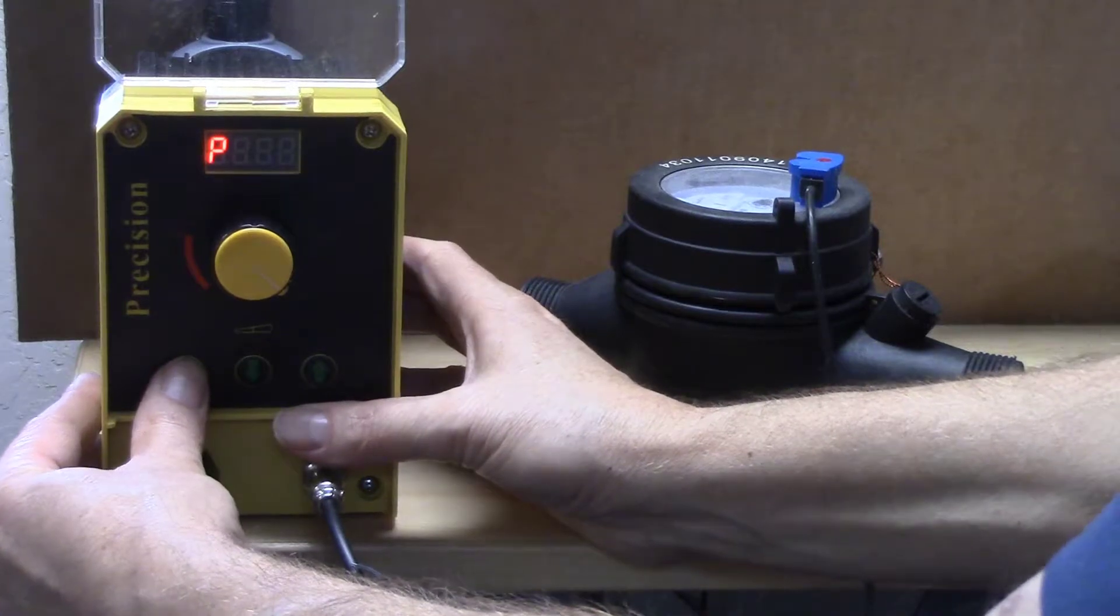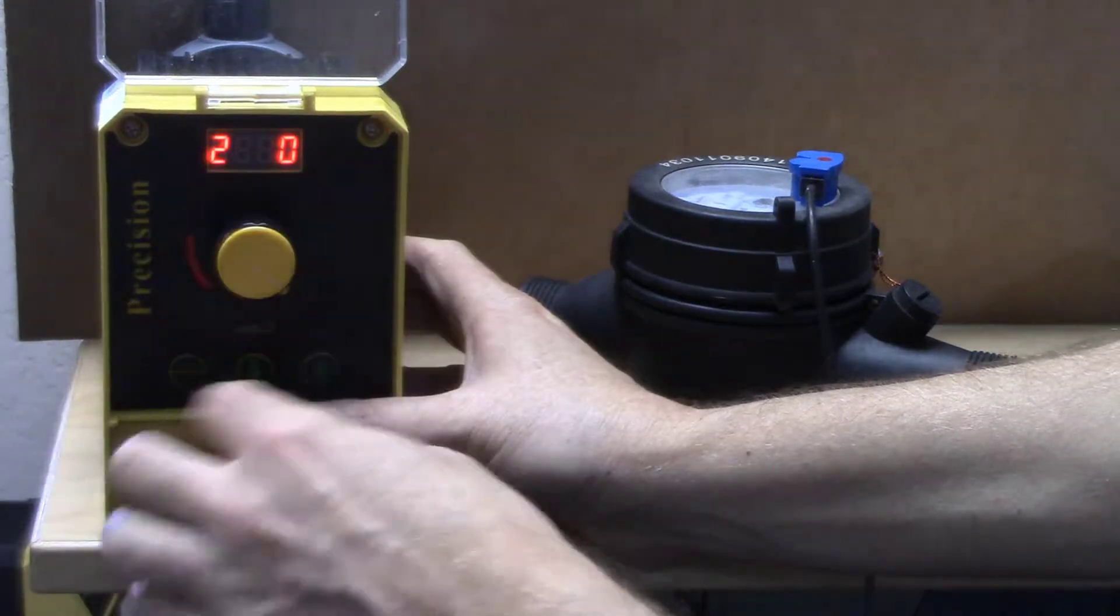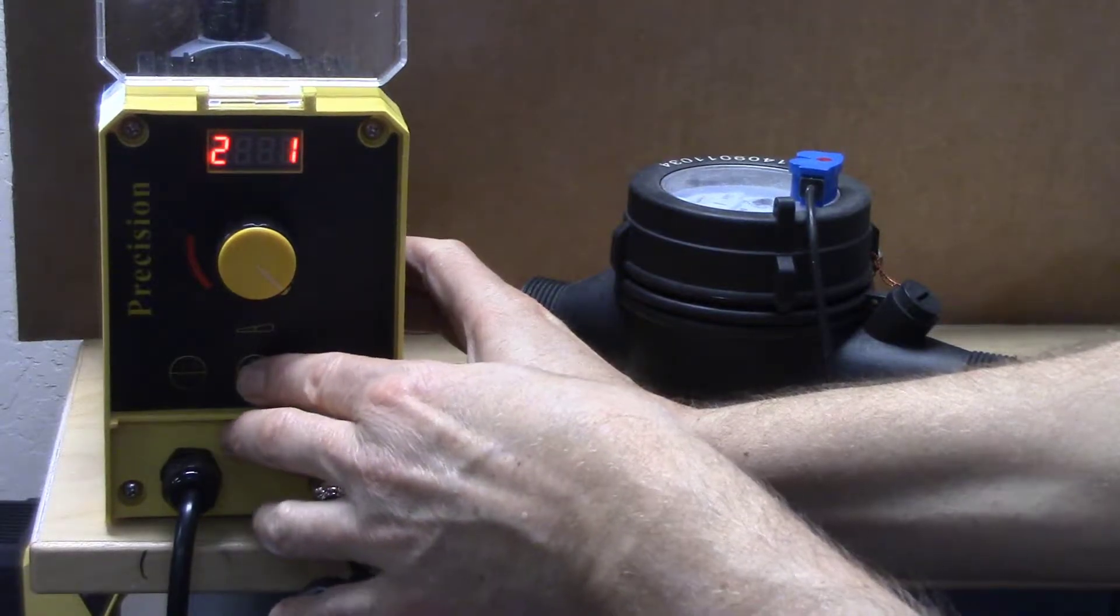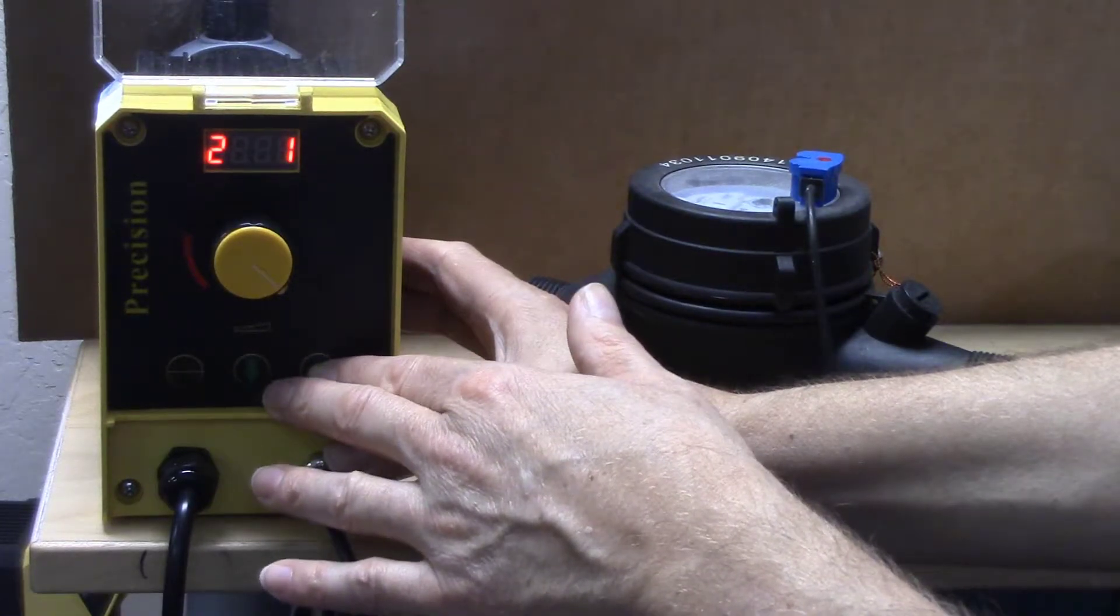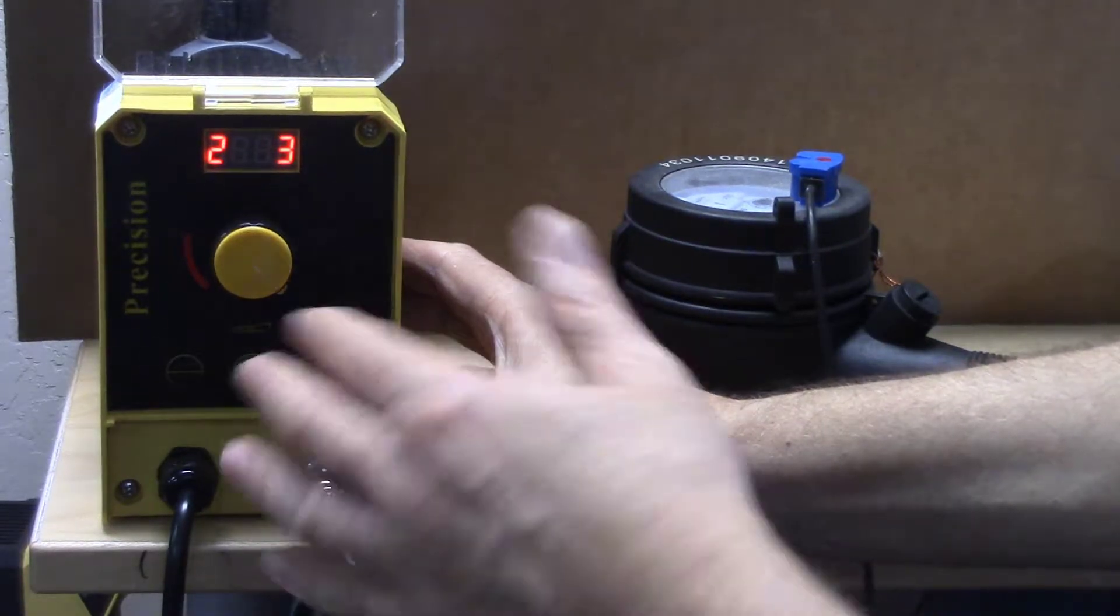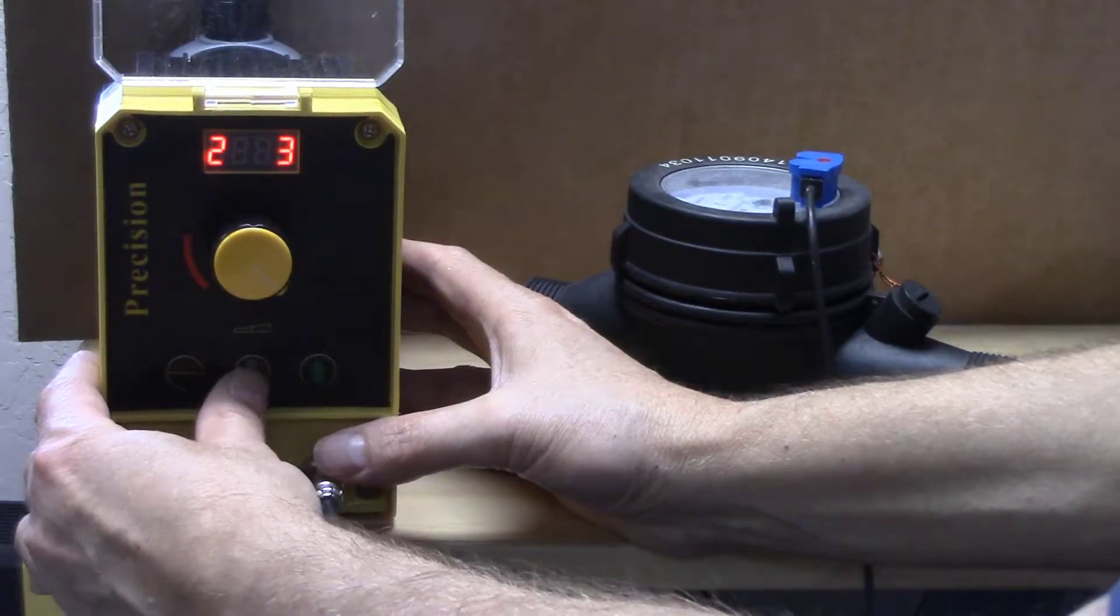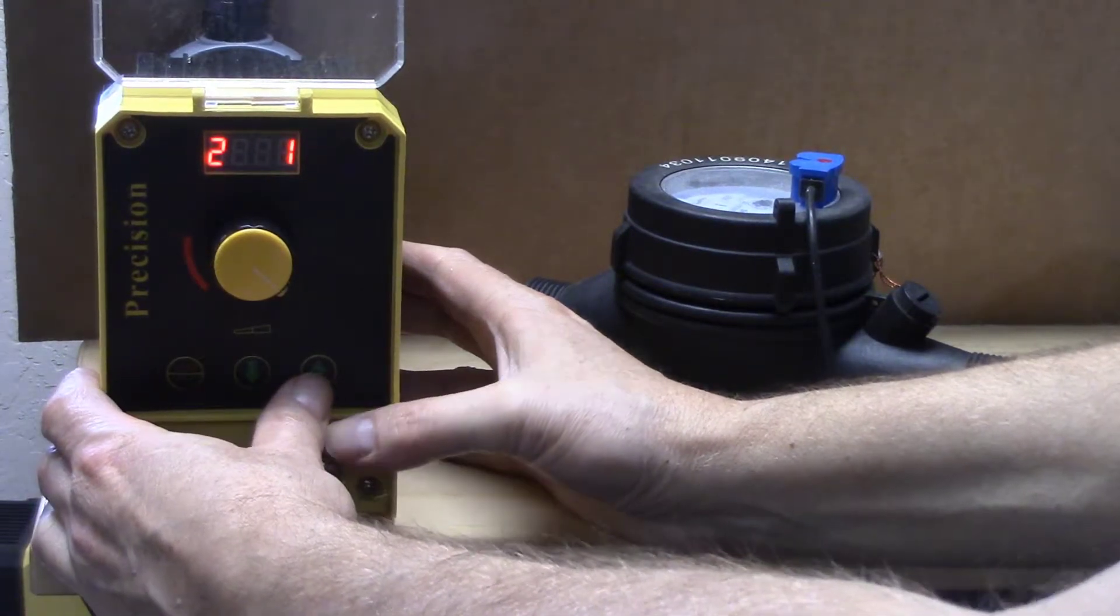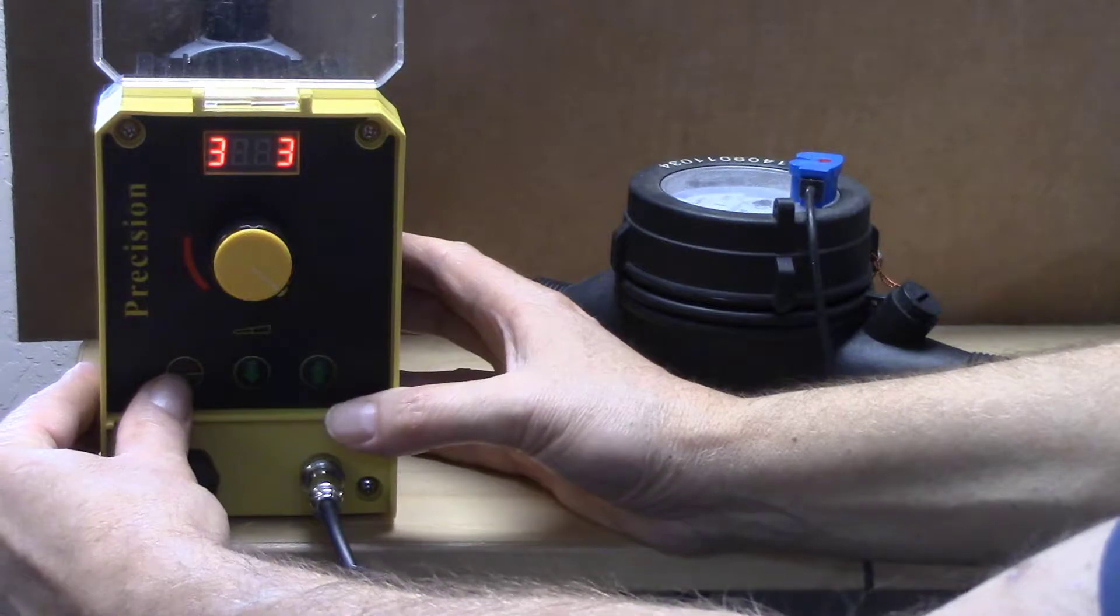Parameter two has the options zero, one, two, and three. Zero is manual mode, one is pulse multiplier, two is pulse divider, and three is a function that's very rarely used for our applications. Most of the time you'll have the pump set either on zero for manual or one for pulse multiplier.